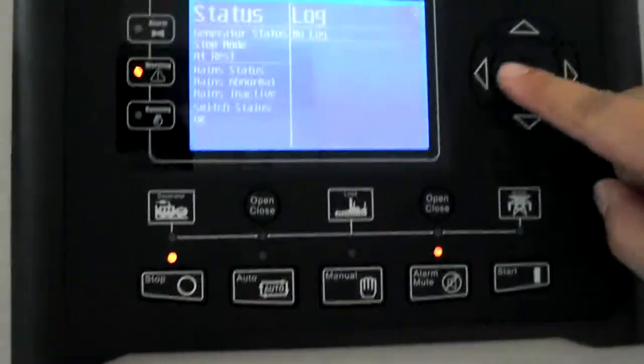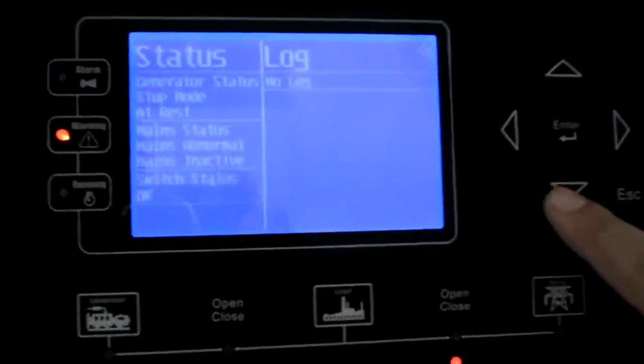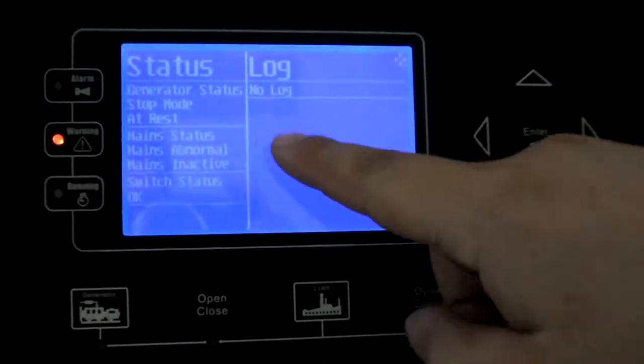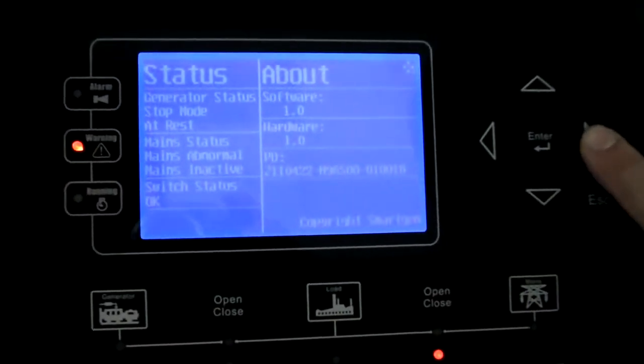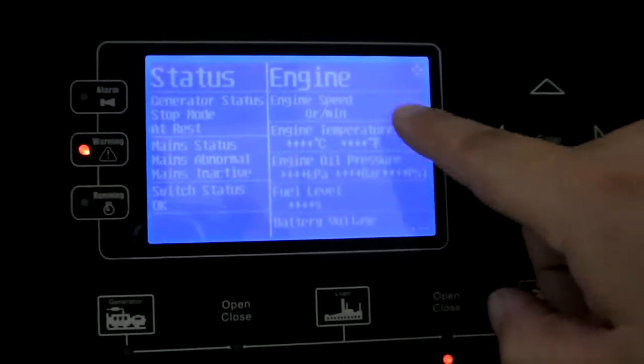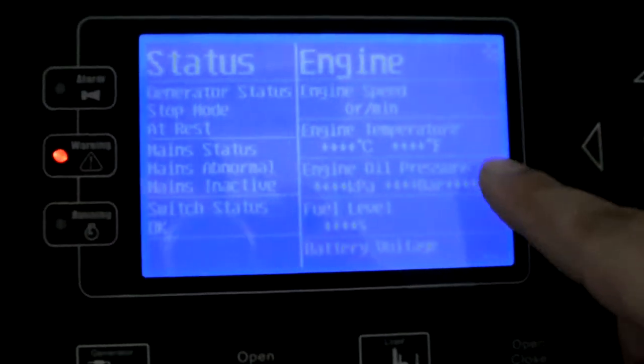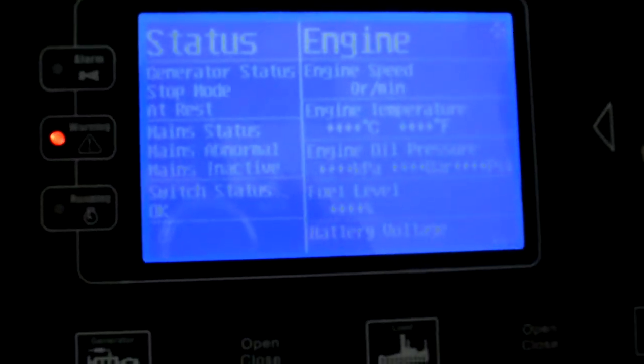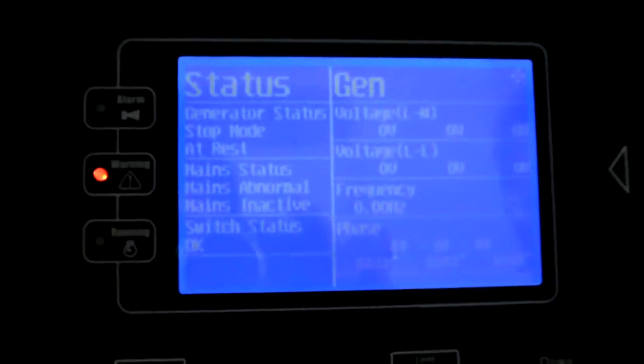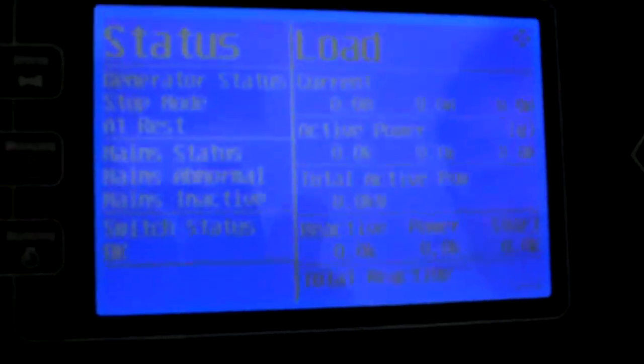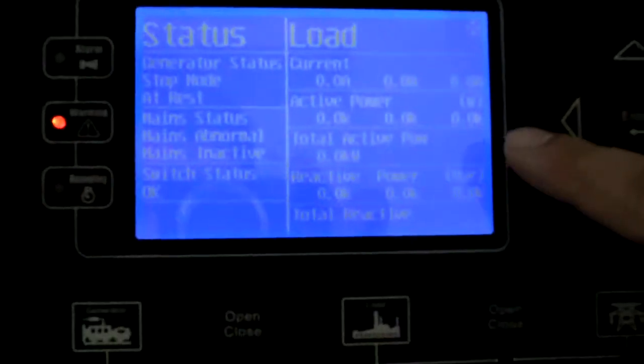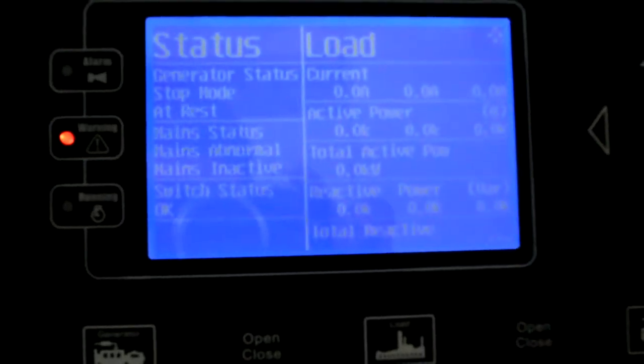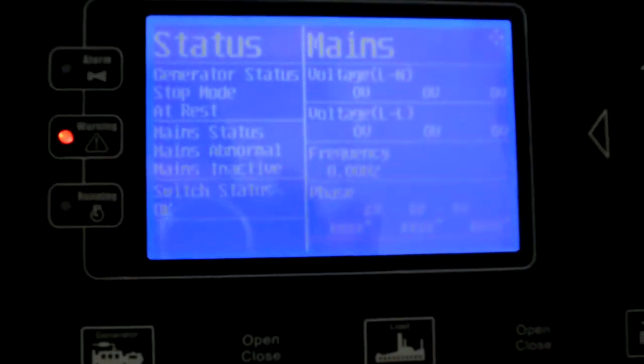You see, parameters can be shown from the generator into the controller. Status of generator, engine, including engine speed, engine temperature, engine oil pressure, fuel level, battery charge, battery voltage, voltage, frequency, phase, and load current, active power, total active power, apparent, reactive power, everything.